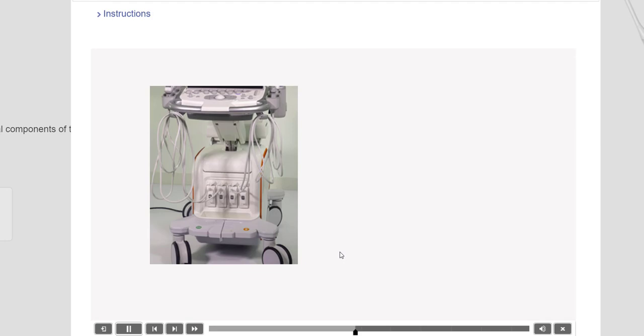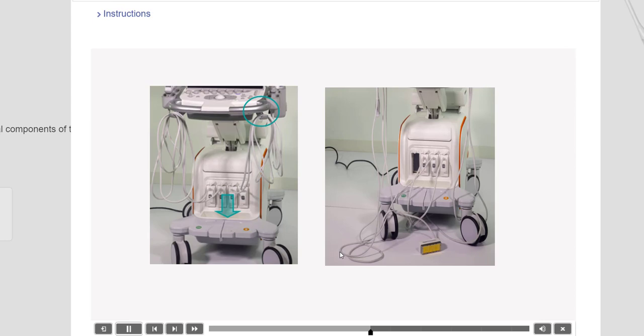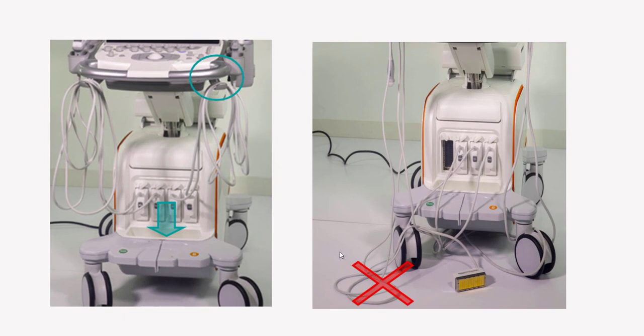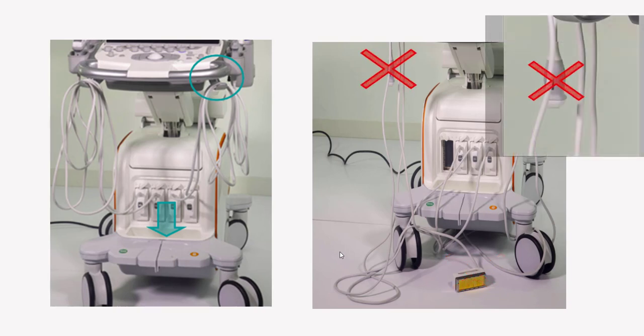Create a good habit and always secure cables to the hooks and holders after every use. The storage shelf below the transducer connecting system can serve as temporary storage for the transducer connectors when not locked into the system. Avoid leaving cables on the floor. The floor is unsanitary. Additionally, when cables are unattended, cable damage is likely. The wheels on the ultrasound device can roll over and pull the cables. Damage will occur to the connections and wiring inside. Secure transducers and holders along either side of the ultrasound unit to prevent unintentional damage.